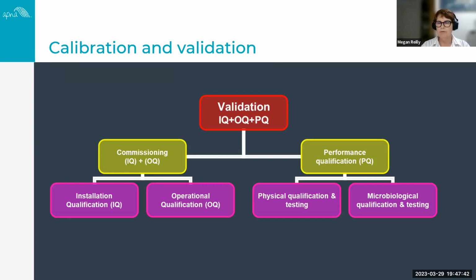And Appendix F in NZS 4815 describes the validation process for steam sterilizers really well, as do the IPC, RACGP IPC guidelines. Validation is repeated annually, after your machine is initially commissioned, and also every time there is any significant change made to the parameters. So when we're talking about time, temperature, pressure, but also any changes to packaging or loading specification, which provides us the greatest challenge to that process.